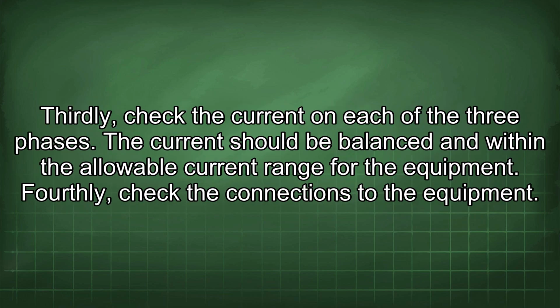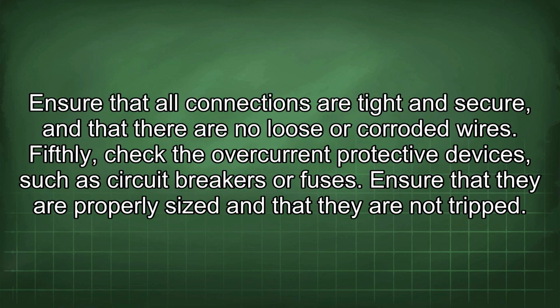Thirdly, check the current on each of the 3 phases. The current should be balanced and within the allowable current range for the equipment. Fourthly, check the connections to the equipment. Ensure that all connections are tight and secure, and that there are no loose or corroded wires. Fifthly, check the overcurrent protective devices, such as circuit breakers or fuses. Ensure that they are properly sized and that they are not tripped.